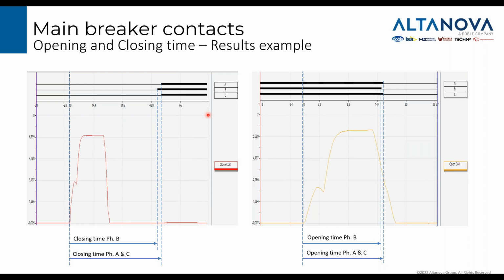Let's see a few simple examples for the close and open operation. As I said before, the timer needs to start when the coil is energized. So in both situations, the timer starts from here, and we can see that sometimes the main contacts are not well synchronized. This is also a measurement that is important to be done, because if one of the contacts is too slow, it will create a problem in the network and in the circuit breaker as well. It is important that you use a method to measure with high accuracy the switching time, the tripping time of the main contacts.